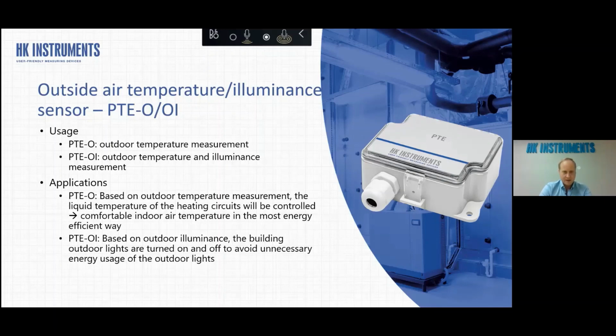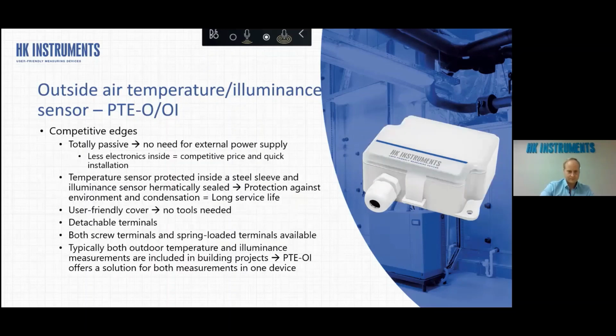So typically these illuminance sensors have been active and needing power supply, but this one is working with a similar kind of principle as the thermistors. So it's totally passive. So you don't need to bring up the power supply, but instead you can just bring 2 wires for the outdoor temperature and the illuminance to your system. Oh, actually, now that I said a bit wrong, that one is actually the combination of the outdoor illuminance and the temperature. But basically we have also, you can choose between just the temperature for outdoors or the combination. It's up to you. They are basically very similar.